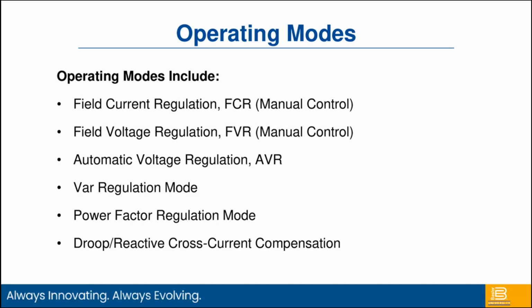I have to have a source that I'm paralleled against that is going to control voltage. So that's why when you're running in a VAR mode or a power factor mode, the rule of thumb is 10 times bigger, but there's obviously some room around that. But I want a source that's going to regulate voltage. So in this case, this particular generator may not be able, or should not be able, to move utility voltage around in parallel with the utility. So I can run in a VAR mode. I can change my excitation levels, and I'm not going to change the voltage because the utility is regulating the voltage. So now I'm just changing the amount of load out of that particular machine.